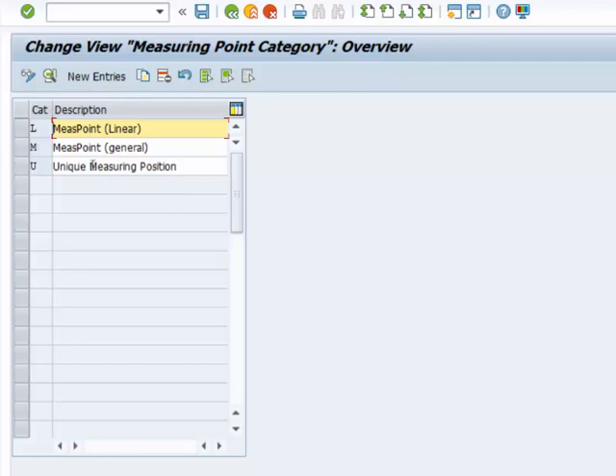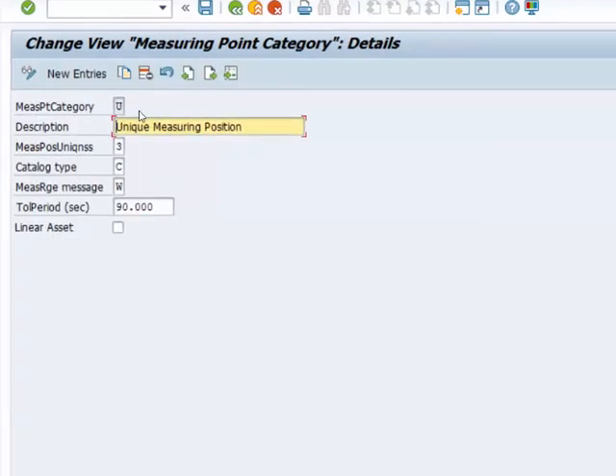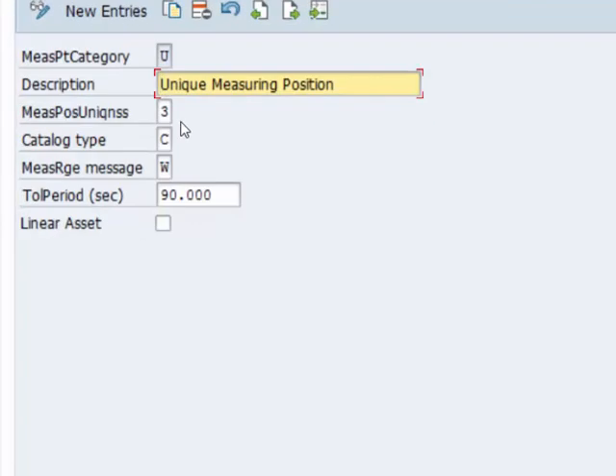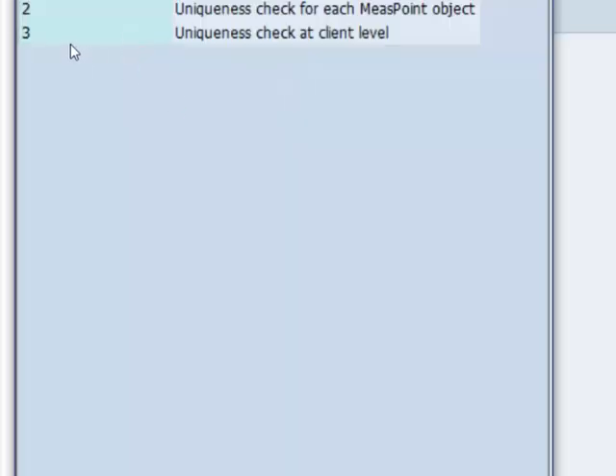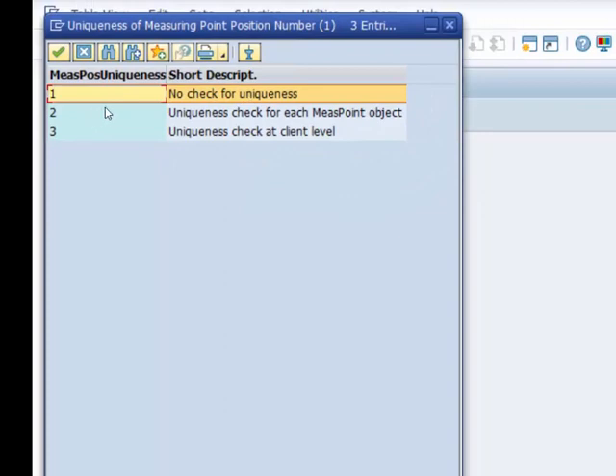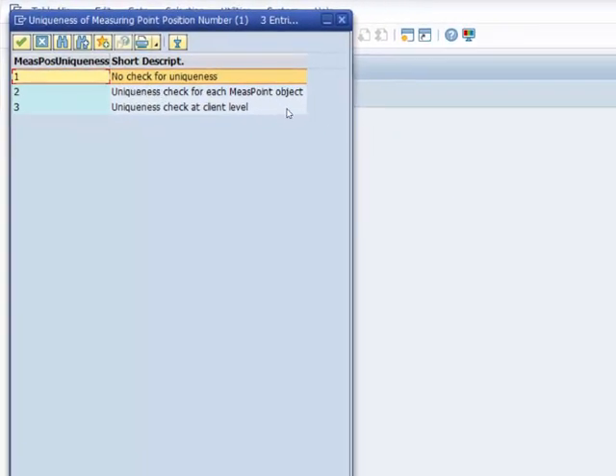So let us go ahead and open one of them. So again we have the category type here that is U. We have the description and then we have measuring position uniqueness. And what this does is that it prevents points from being defined more than once. We have a few choices here. We can either fail to check for uniqueness, we can check for uniqueness within the object or we can check for uniqueness at the client level.